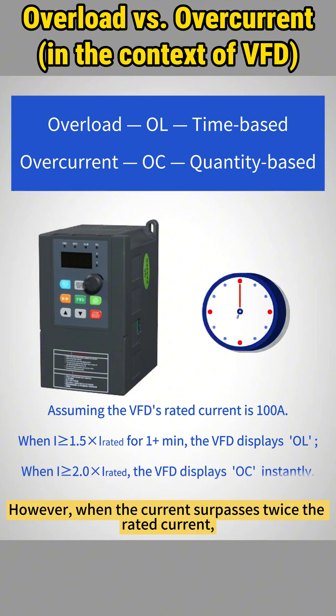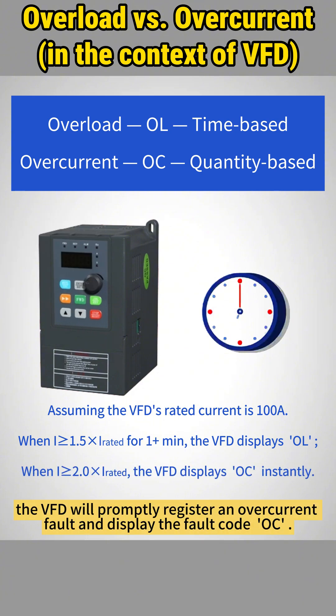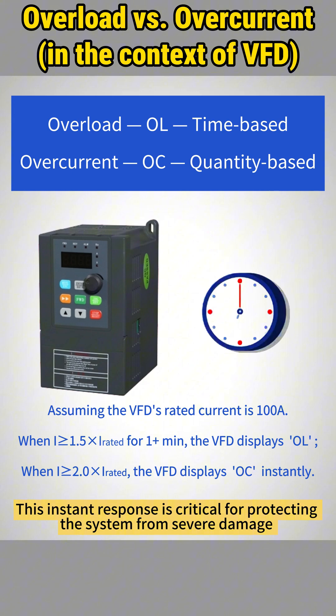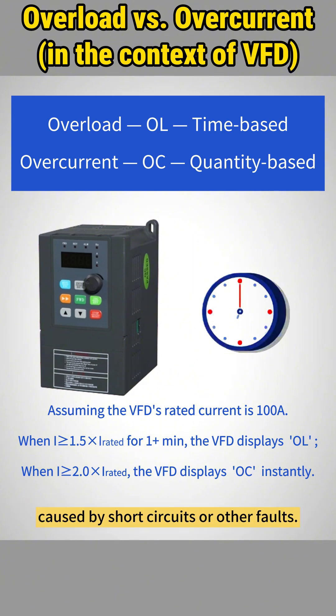However, when the current surpasses twice the rated current, the VFD will promptly register an overcurrent fault and display the fault code OC. This instant response is critical for protecting the system from severe damage caused by short circuits or other faults.